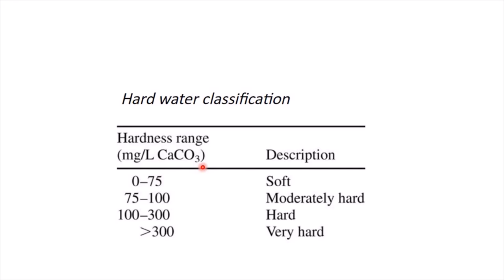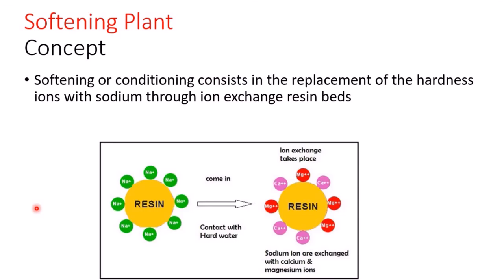Water hardness is classified based on the concentration of calcium carbonate in the water. The water is considered soft when calcium carbonate concentration is between 0 and 75 mg/L; moderately hard between 75 and 100 mg/L; hard between 100 and 300 mg/L; and very hard above 300 mg/L.